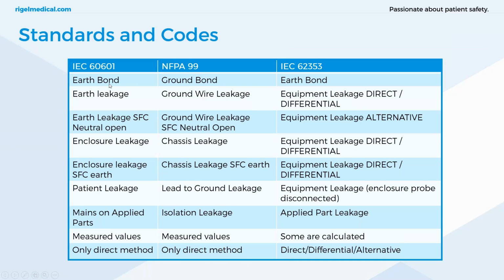This is something which compares the different standards and codes. So a standard is a document which contains technical definitions. It has guidance for manufacturers, for procedures. It's not necessarily mandatory, it has mandatory requirements, but compliance to that can be voluntary. A code such as NFPA 99 is a document that's been enacted into law by regional or national authorities, and they have jurisdiction to state that an engineer or a biomed contractor is legally obliged to comply with these tests and these codes.